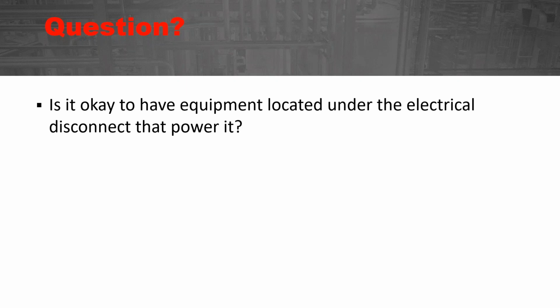And we're seeing this more and more in industrial control panels, where there's a disconnect put in front of the industrial control panel. That way, when you turn off power, you're turning off the power going into that. You can open the cabinet up, and once the equipment is in an electrically safe work condition, then you can take off PPE.